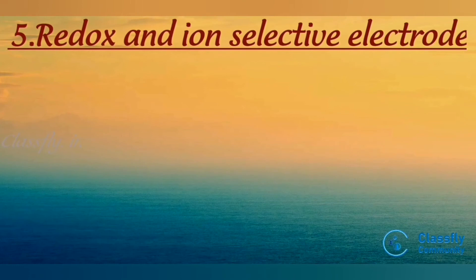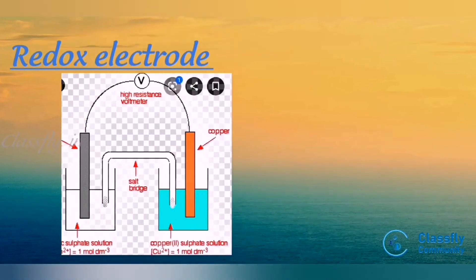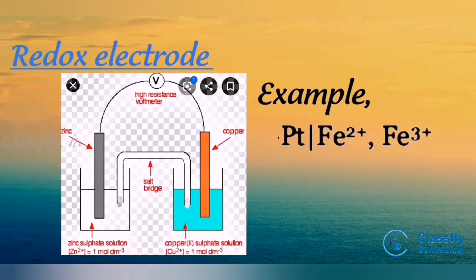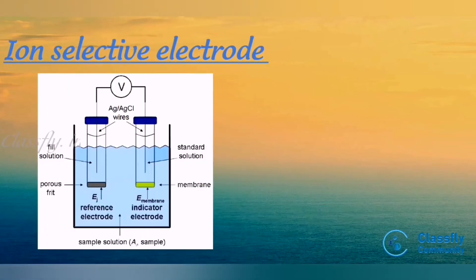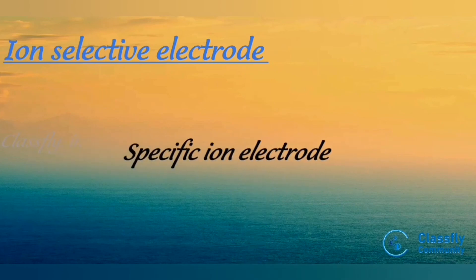The fifth type is the redox and ion selective electrode. This is divided into two subtypes. In a redox electrode, an inert metal like platinum is dipped in a solution containing ions of an active metal in two different oxidation states — for example, Pt | Fe²⁺, Fe³⁺. In an ion selective electrode, a membrane is in contact with a solution with which it can exchange ions — for example, the glass electrode, also known as a specific ion electrode.